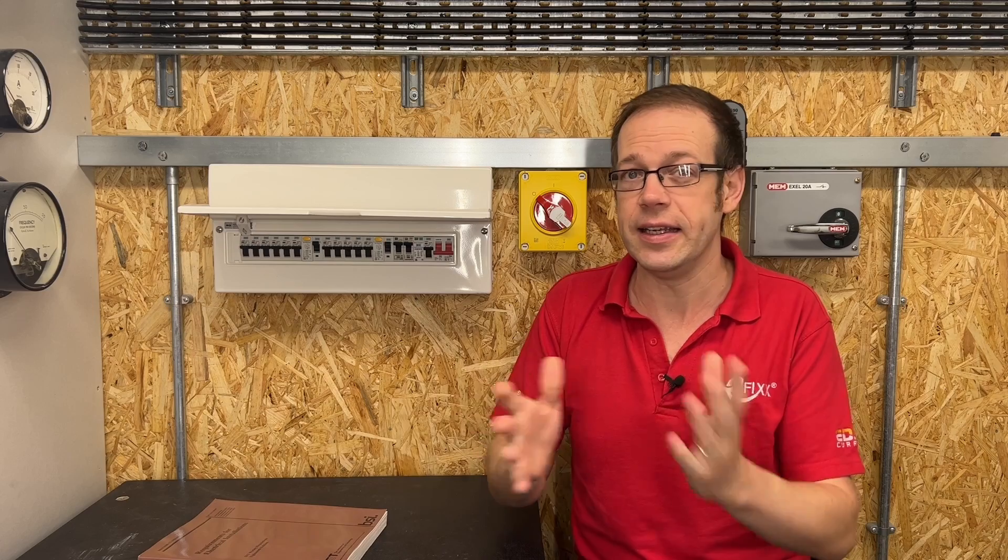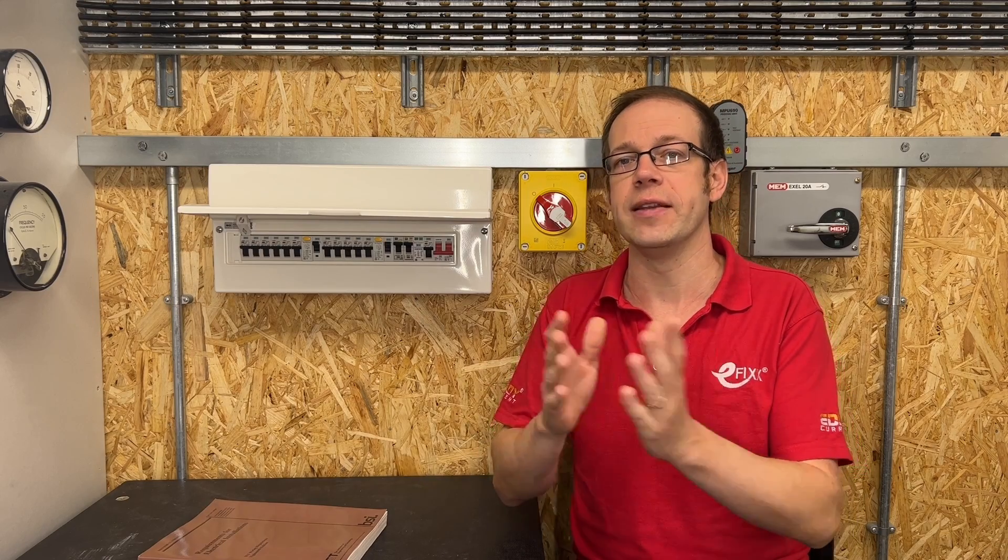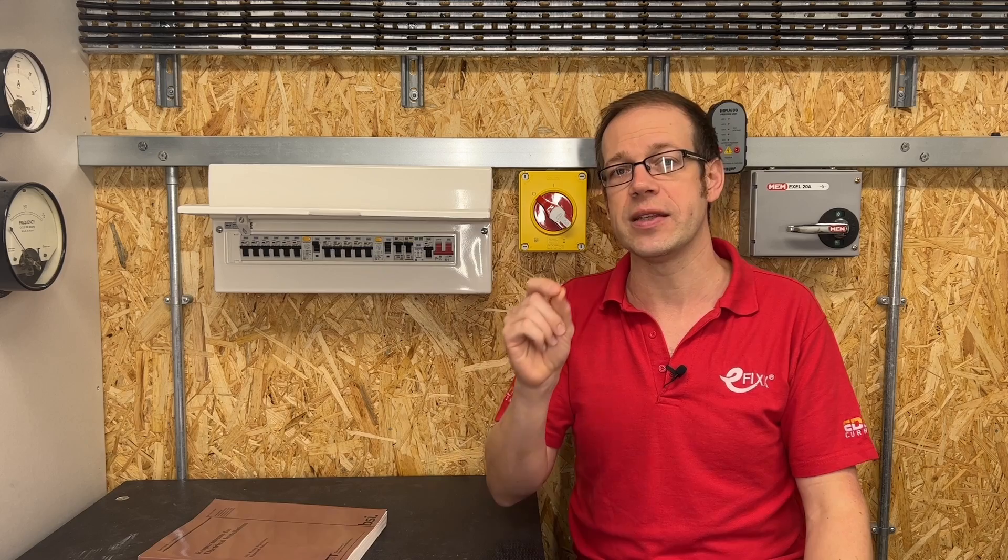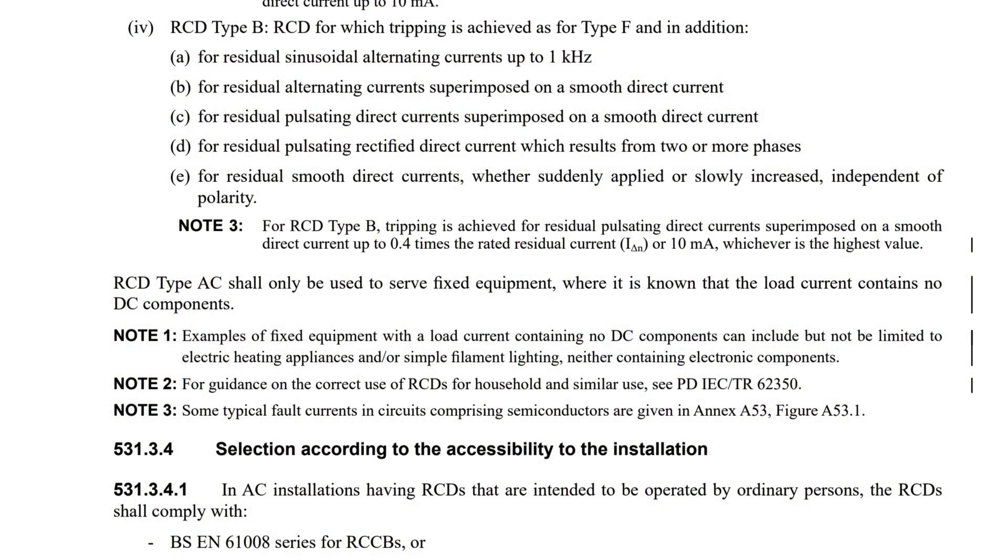So, it seems with all the DC leaky loads people are connecting to our electrical installations, the type AC RCD is a thing of the past, and it seems the Second Amendment is reinforcing this idea. After defining the different types of RCD, Regulation 531.3.3 states, RCD type AC shall only be used to serve fixed equipment, where it is known that the load current contains no DC components.